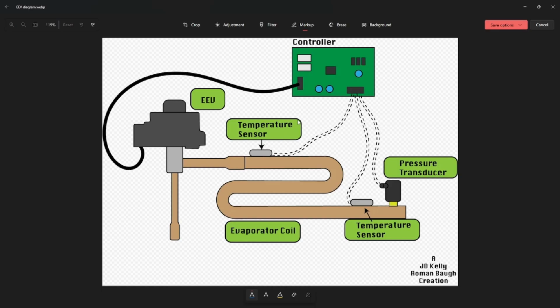The temperature sensors, however, are important to make note of because these temperature sensors fail so much. Most of the time when you have an issue with an EEV, it's because your temperature sensors have stopped reading properly. Temperature sensors can be checked just like any other type of sensor or thermistor by checking the resistance based upon a known temperature. They all have thermistor charts or ohm charts. They're going to be in their respective service manuals.